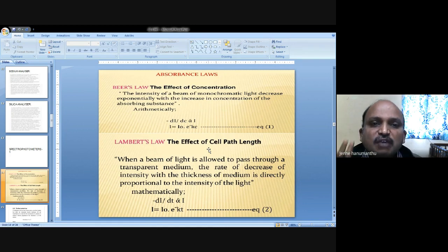So we can overcome two parameters. First, reflections are overcome by using a smooth and polished surface for the container. Second, scattering can be overcome by completely dissolving the sample in the solution.